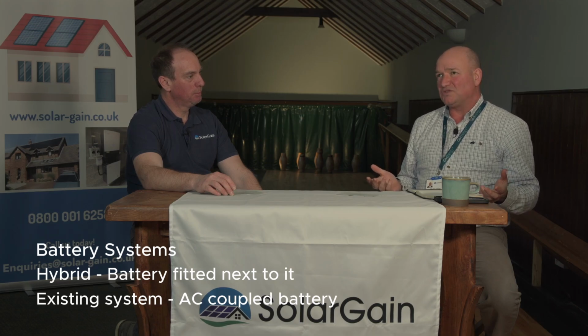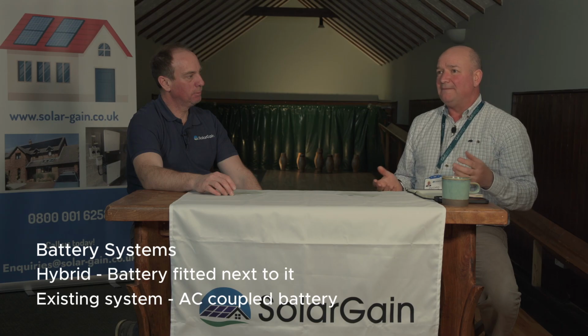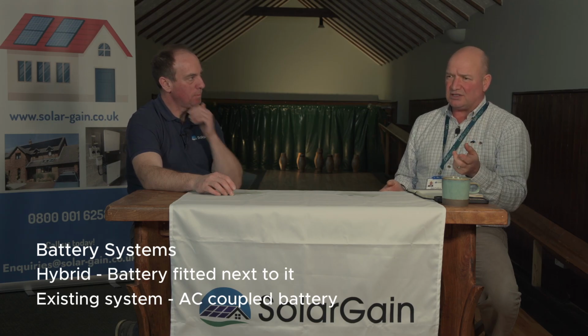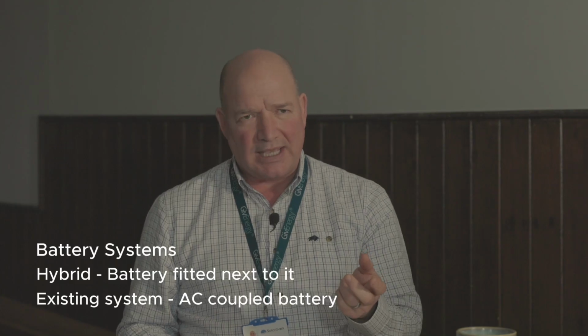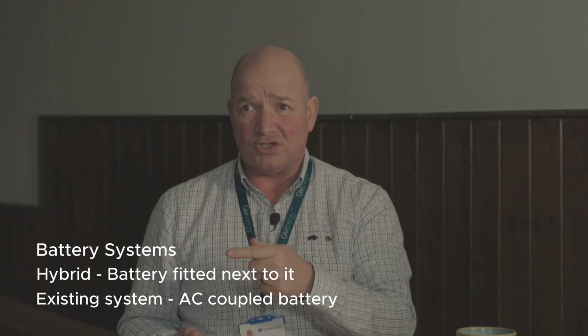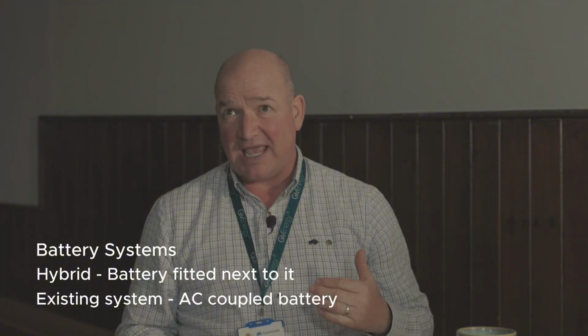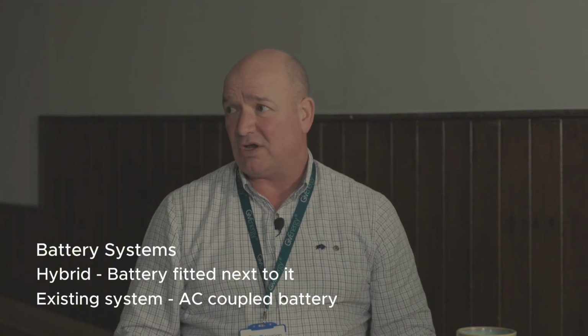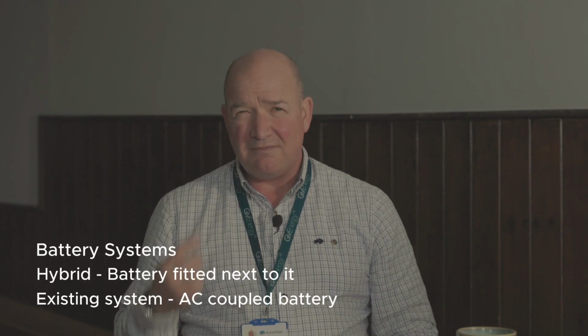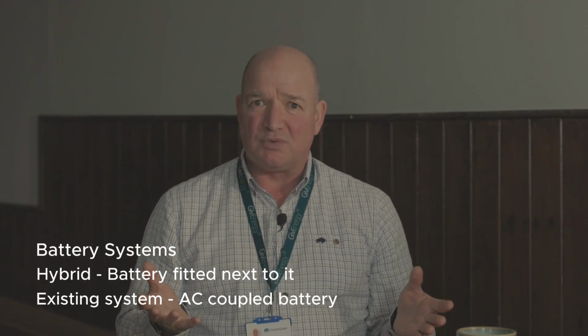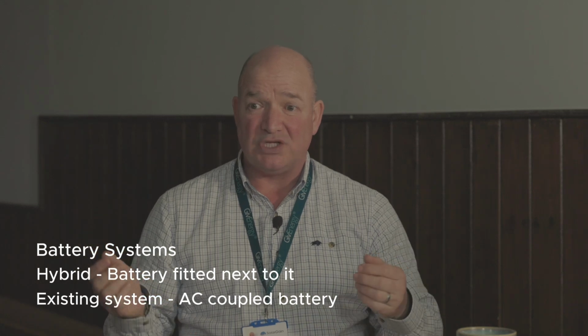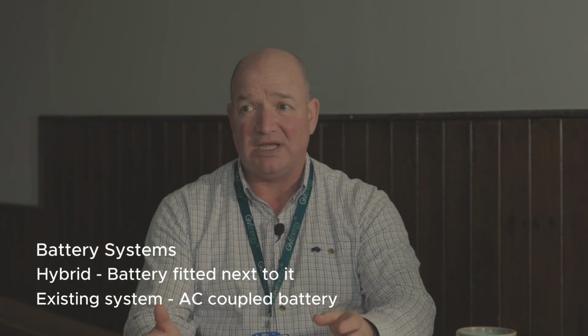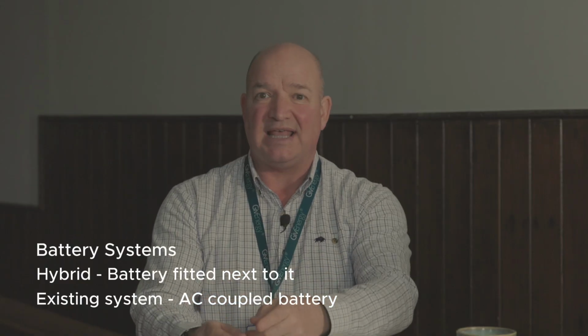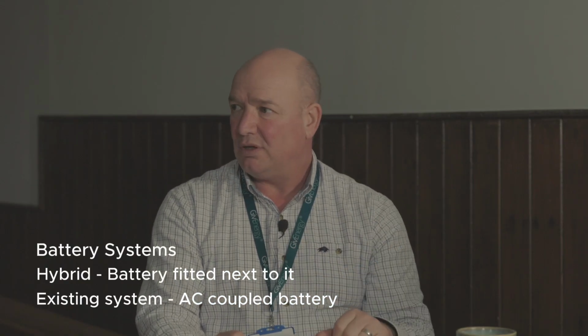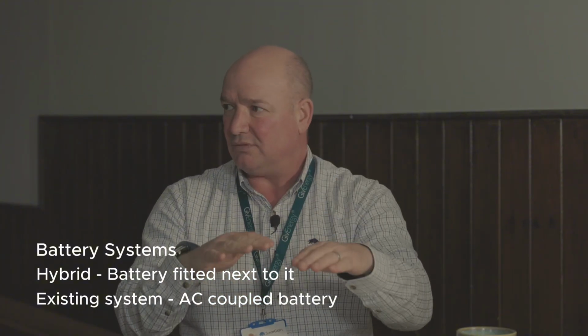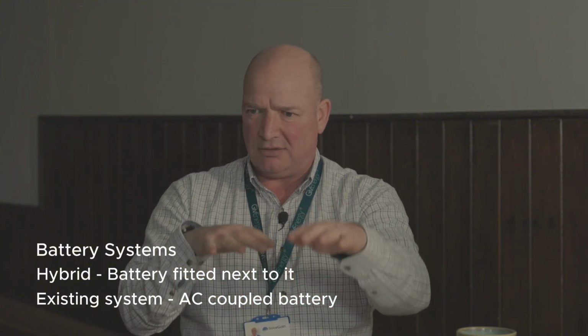So when that voltage starts to go out to the grid, you've got a thing called a CT clamp, haven't you? It's a current transformer. Is that what it stands for? Yes. So that monitors the direction of current and the amplitude, the amount of current that's going in or out. So in my simple brain, what happens when you have an AC coupled battery is that as the current starts to pour out to the grid, the CT clamp sees that and tells the thing to switch on and start power matching however much is going out. So you're almost kind of manually adjusting, albeit with a slight delay.